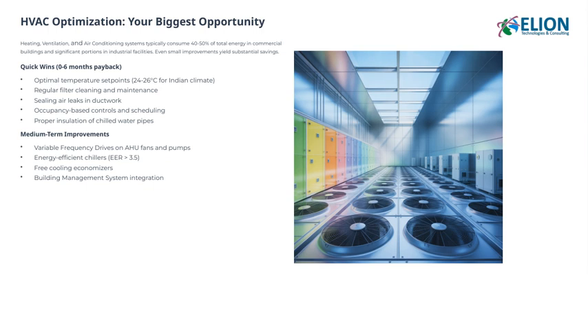Moving into medium-term improvements, things like installing variable frequency drives on air handling unit fans and pumps can optimize their operation. Upgrading to energy-efficient chillers with a high EER, above 3.5, is another effective step. Additionally, incorporating free cooling economizers and integrating your systems into a building management system allows for smarter, more responsive control.